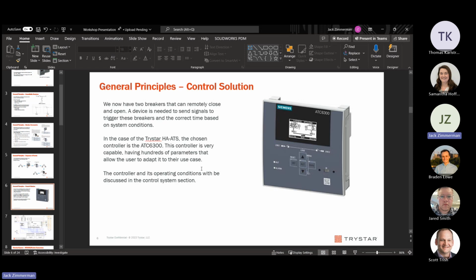We do have to do some initial programming though, because this controller - if you look on the box, it has a bunch of German words on it. It's all 400 volt, 50 hertz, so we have to configure it into 60 hertz, 480, or whatever the American standards are for the companies we're shipping it to. There's a way to go through the controller and program each item by hand, or you can plug something in, do a power config, and upload it all. But it's a good question - there's another deliverable beyond electrical and mechanical, and that's the parameters for the controller. That's a deliverable from the engineering department for these things.